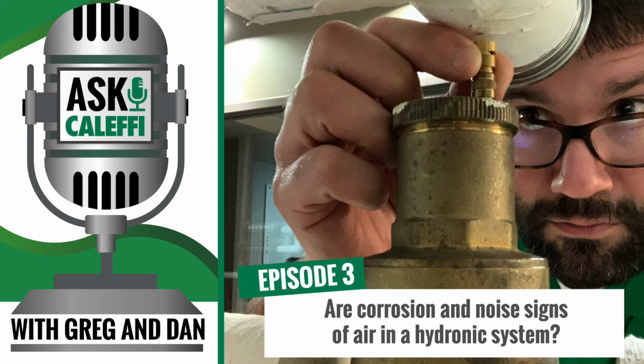You got it. I mean, you take a 2-inch brass model, and I know we kind of picked that because that's the point where you can cross over from brass to steel. And you take a 2-inch model rated at 37 GPM, and you have a boiler or a system that's 48 GPM. Yeah, you have to step to that bigger size. If you don't, it's just not going to perform well for you. No, you're going to have a pressure drop in that, which is no good.